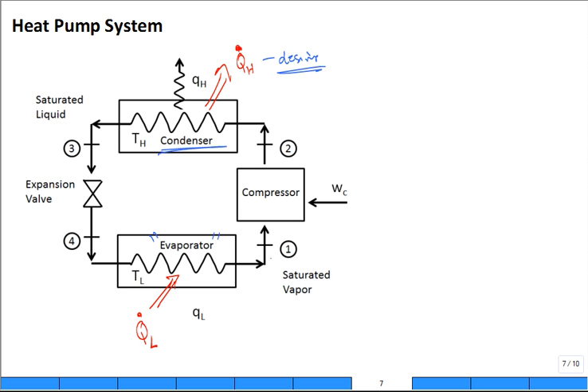And the outside unit has cold air. Let's say it's zero degrees F outside. Really cold day. It will take some energy, some heat out of that zero degree F. It'll drop it. The air that goes across outdoor unit will maybe come negative five, from zero to negative five. It'll cool the outside and help provide heating to the inside. So maybe you buy one kilowatt of electric power. Maybe you get two kilowatts heat transfer from the outside. That's already cold, but you're making it colder. And then you would get three kilowatts of thermal heat into the building.